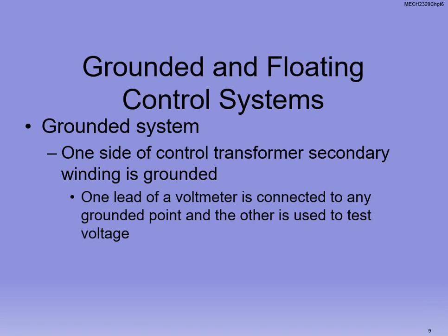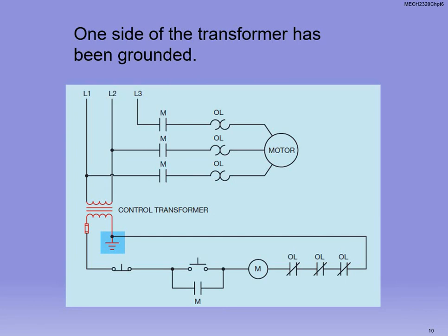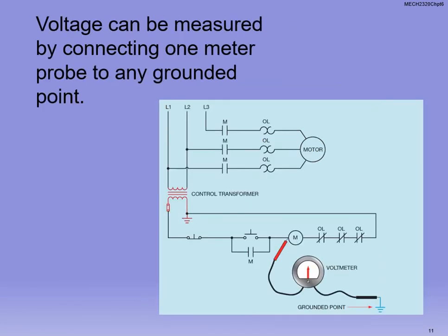So you'll be doing this in your lab as well, all right, but you're going to use a multimeter for this. And we're going to use the voltmeter to check our voltages and make sure that everything's working properly. But it does depend on the grounding point to come up with our test voltage, all right? So very important here that we understand a few concepts of how to do this, okay? So one basic setup, and most of this is already done in the industry, one side of the control transformer is wired to ground, okay? So that way we can actually take readings on it.